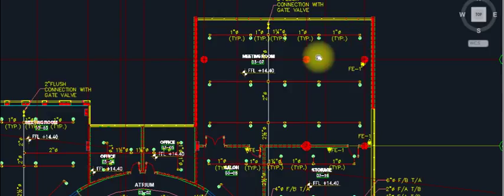If you go to light hazard, the coverage is a little bit more. For example, from here to here is 4.57 meters and 4.57 meters, so one sprinkler covers 225 square feet. So this is light hazard. In light hazard there are some projects, say a gym, mosque, church or hospital. But ordinary hazard includes offices, buildings, education systems and everything. And we have extra hazard as well.